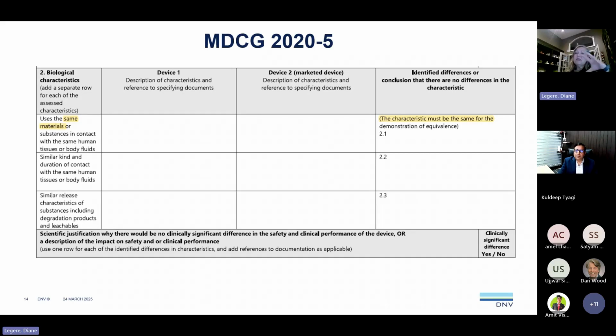I have it in a later slide, but because you've brought this up right now, the struggle with equivalence is you've put together your whole entire technical portfolio and you've submitted it, and you've chosen equivalence because the equivalent device has clinical data that you don't. So that's the other thing. You have to look at what clinical data they have, and if it meets your needs for safety and performance to meet GSPR 1, that you have that data to show that, based on the state of the art, you are state of the art because of this equivalent. Even I'm still making that mistake.